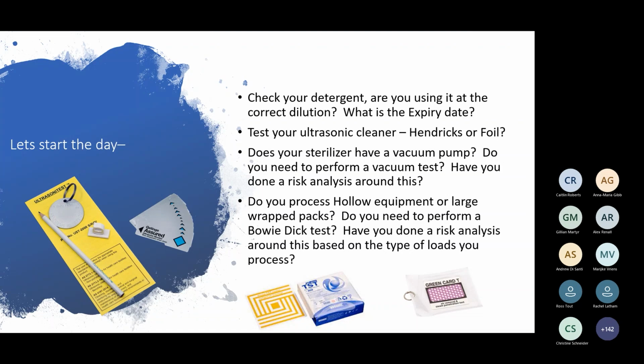So basically, you need to know what your machine is. So if you've got, let's pick on MELAG. A lot of people have MELAG out there. So if you've got a 23S machine, you don't have a vacuum pump. So there is no way that you can do a vacuum test. Your machine's never going to pass it. So you don't need to do a vacuum test. If you have a 29VS, a 23VS, V stands for vacuum. So you have a vacuum pump. So you need to test your machine.